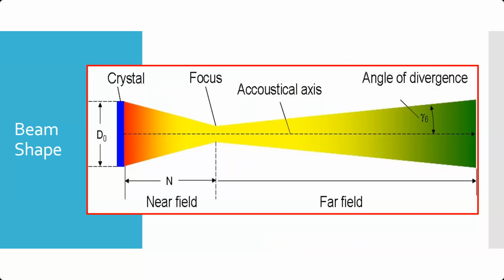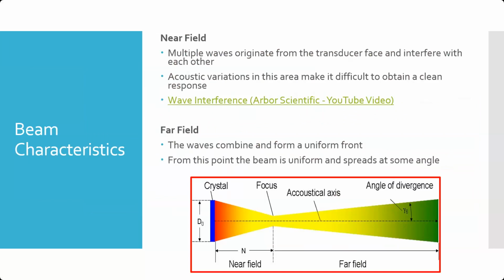And then you have what's called the angle. You can calculate the angle of divergence based on the frequency and that kind of thing. So we have to be aware that this will affect our tests. So in that near field, because you have all those waves kind of coming together and crossing up at the focal point, they're going to interfere with each other, and we can't get a clear indication. Now, what we can do, there are some probes that have what's called a delay line in them. It's a piece of acoustically transmitting material that's attached to the front of the probe that physically offsets it from the part, so that the near field falls in that delay line block before it enters the part. And those are used for finding more surface.